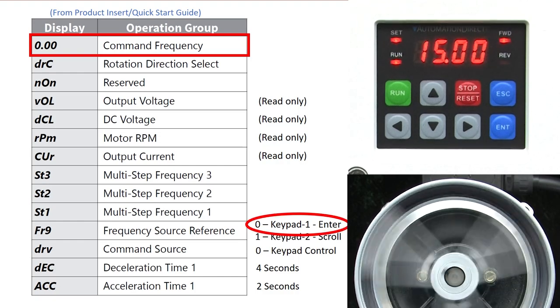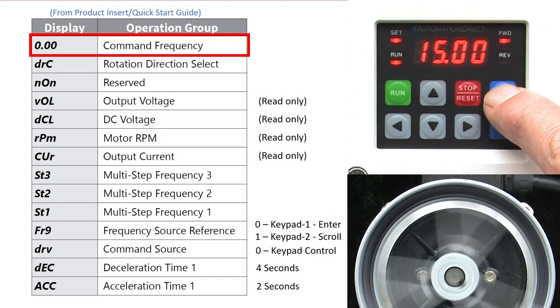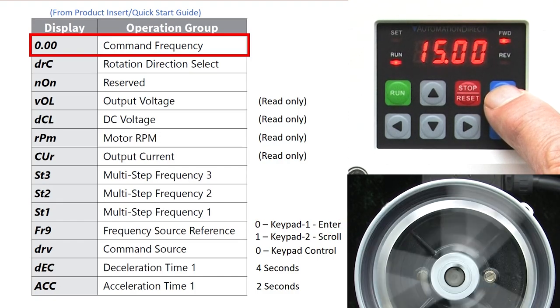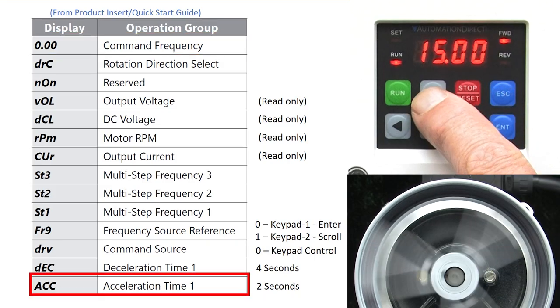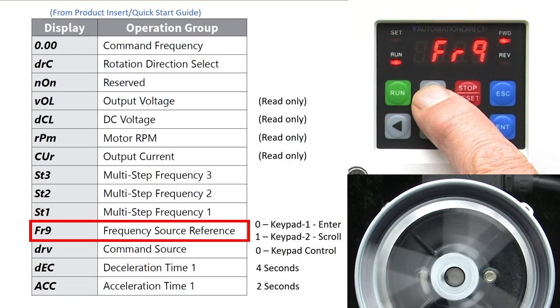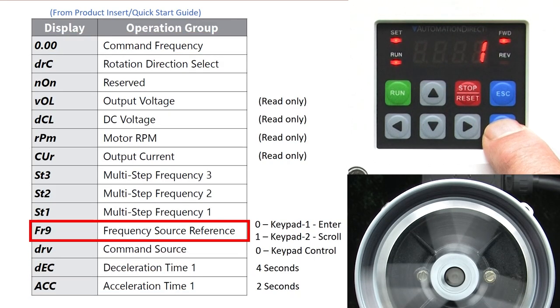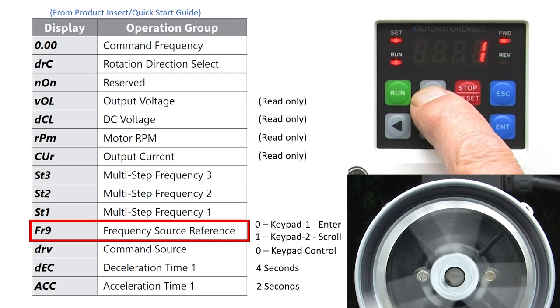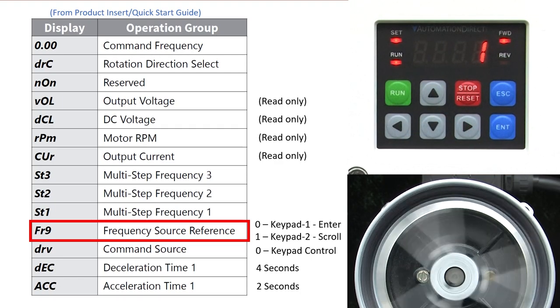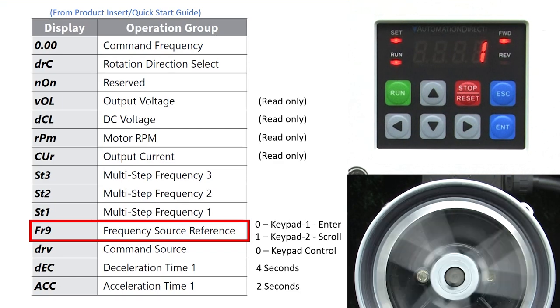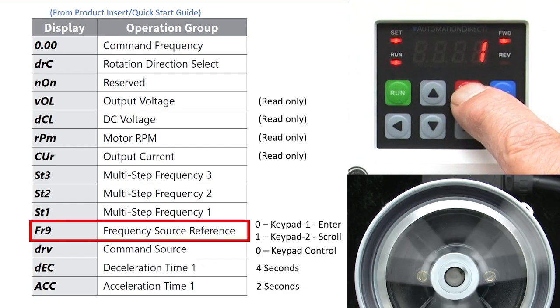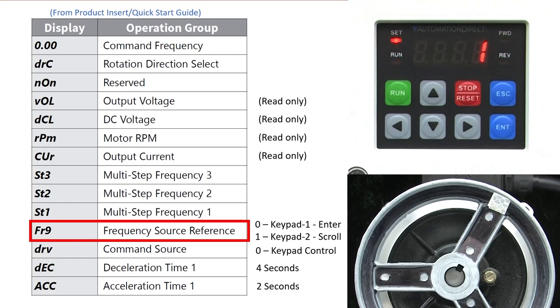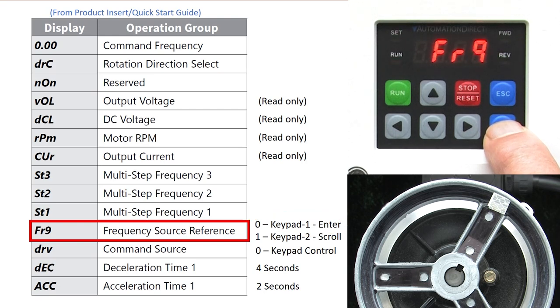Let's switch that to requiring an enter key press to change the frequency. Escape out of here and up arrow to the frequency source select. Enter into that. If I try to change this, nothing happens. Why? Well, you can't change the frequency source while the drive is running. So I'll hit stop, wait for the motor to spin down and now I can change it to a zero for the keypad 1 operation.